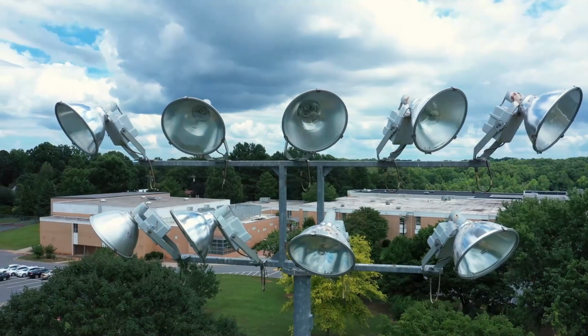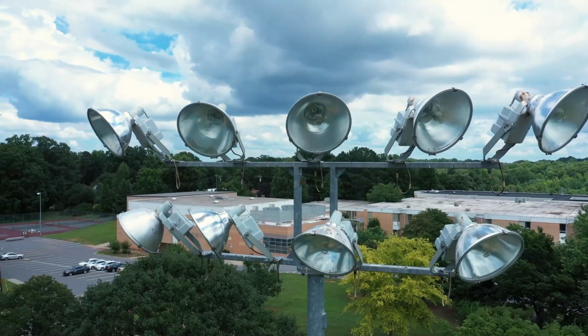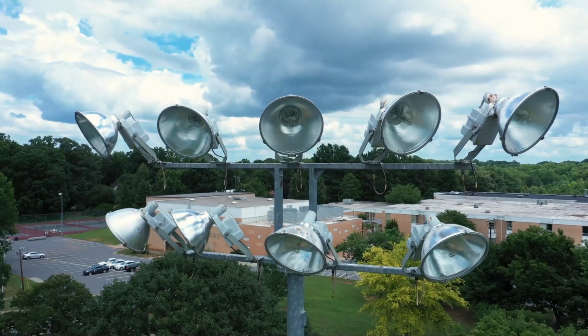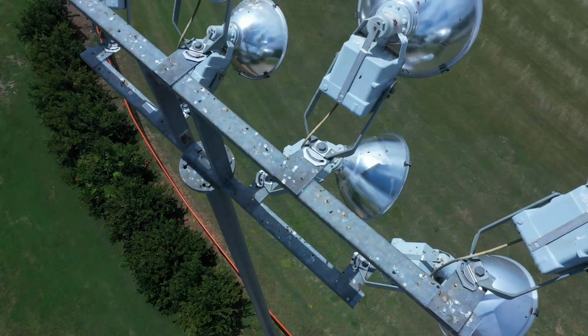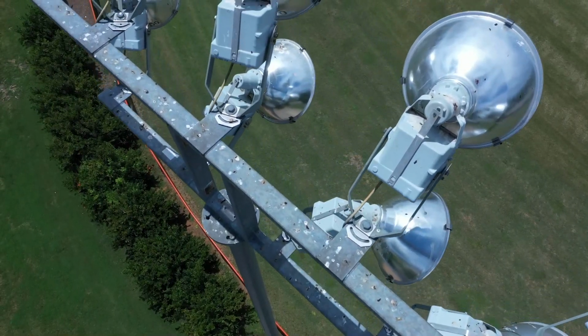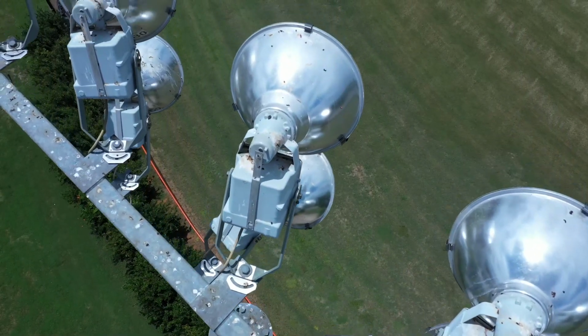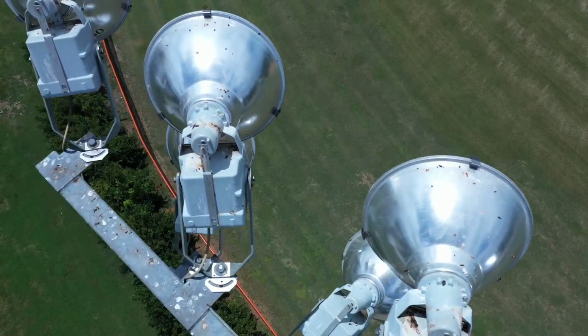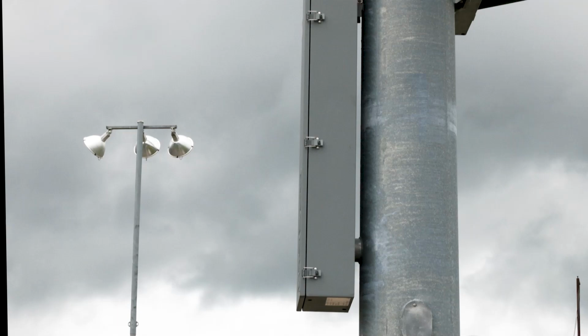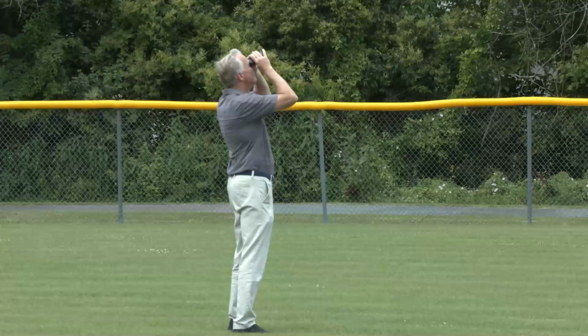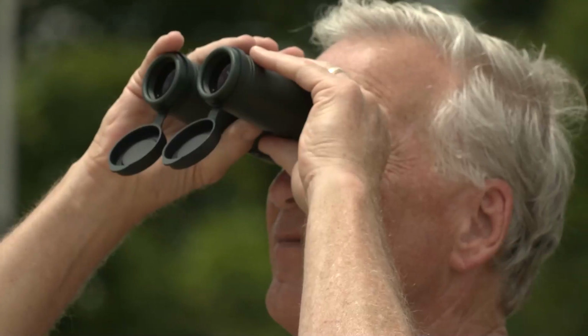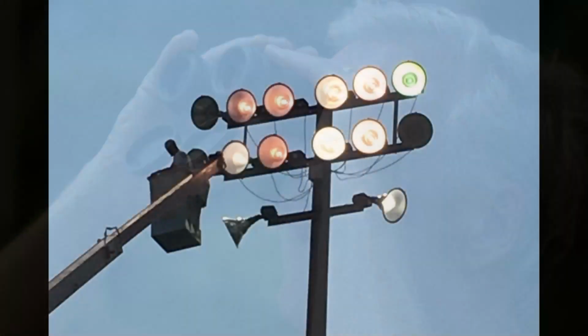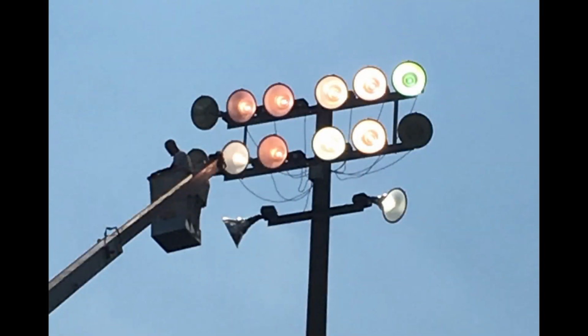When it comes to inspecting the performance of your luminaires, you're going to be looking at the condition of the luminaires as well as their aiming angles. If you're using a bucket truck or lift for fuse inspection or other top of the pole services, you can use that to check your luminaires at the same time. But if your system utilizes electrical components that are located remotely, you can complete the luminaire inspection from ground level using binoculars. The first thing you'll want to check is to see if any of your luminaires aren't operating. If you see an outage, it will require further testing.